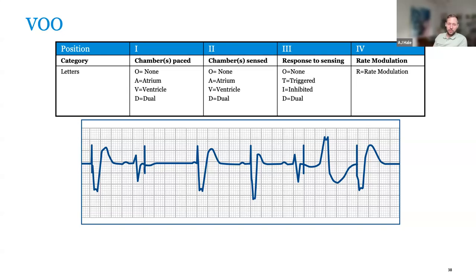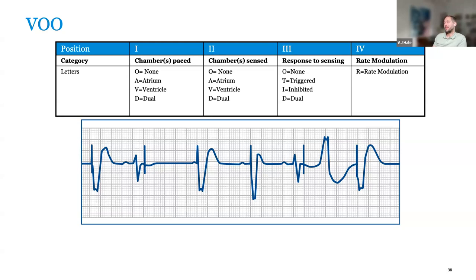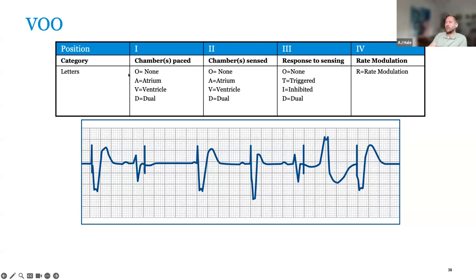The difference between demand pacing and asynchronous: demand is just when the heart needs it — it demands it. Asynchronous covers VOO, DOO, AOO types, which means it doesn't respond to sensing and doesn't bother to sense at all — it just paces at the base rate no matter what.